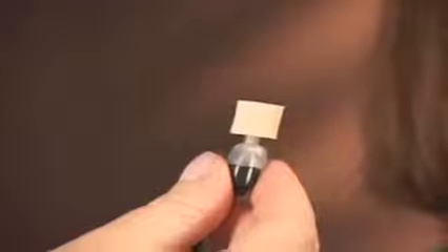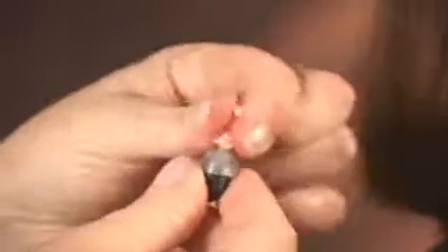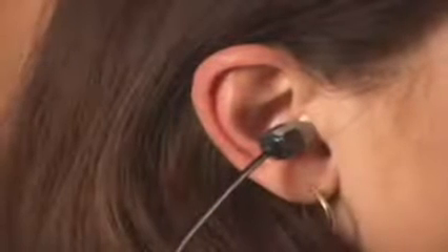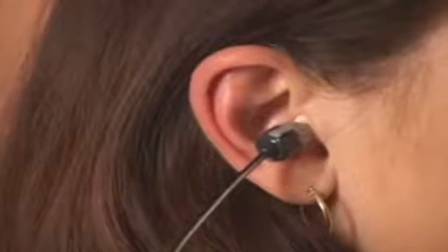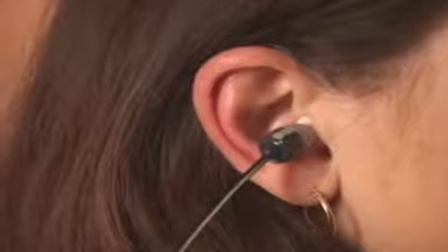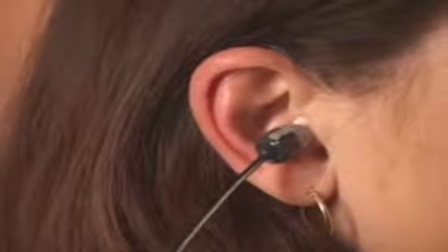Clip the cable to the patient's shirt to keep the weight of the cable from pulling on the ear probe. Compress the foam ear tip by pressing around its outer edge until it is approximately 1/2 its normal diameter. Next, grab the outer ear above the earlobe and gently pull up and backwards. Insert the compressed ear tip into the ear canal and release the ear. The tip will expand in the ear canal and you can start the test.